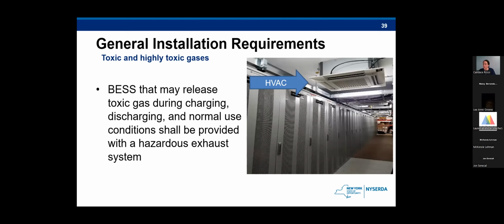The next general requirement is for toxic and highly toxic gases. Systems that are installed indoors and have the potential to release toxic and highly toxic gas during normal use will be required to have a hazardous exhaust system. Some batteries may release toxic gases during normal charging and discharging, and a forced fan system can be used in battery charging rooms and other areas where gases can build up in a contained space. I will note that lithium ion does not release any toxic gases during normal operation, and therefore it's not required for them to have this ventilation.